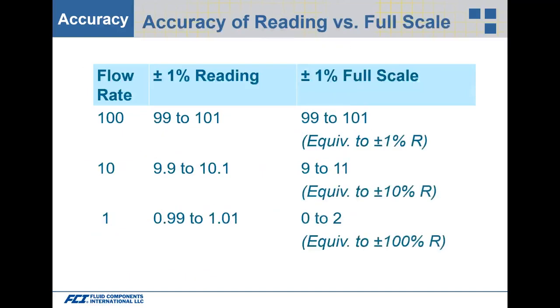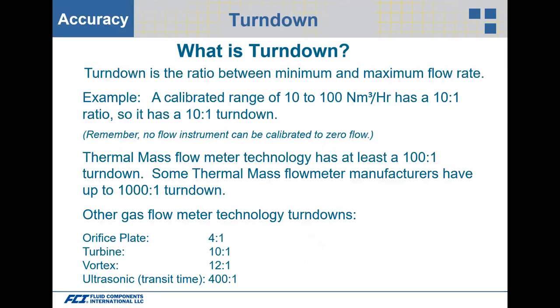The turndown is the ratio between the maximum and minimum flow rate — a flow range of 10 to 100 normal cubic meters per hour has a 10-to-1 turndown. Thermal mass flow meter technology has at least 100-to-1 turndown; some manufacturers go up to 1000-to-1. For comparison, an orifice plate typically has 4-to-1, a turbine meter is 10-to-1, a vortex is 12-to-1, and ultrasonic goes up to 400-to-1.